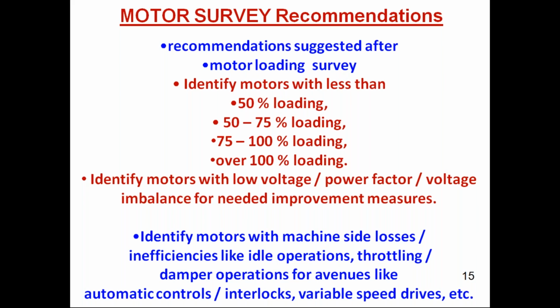Automatically, power savings of around 10 to 15% are achievable. This cost is only 10,000 rupees, whereas a motor costs almost 1.5 lakhs. Instead of replacing the motor, we can just fit an automatic Delstar and achieve the energy savings.